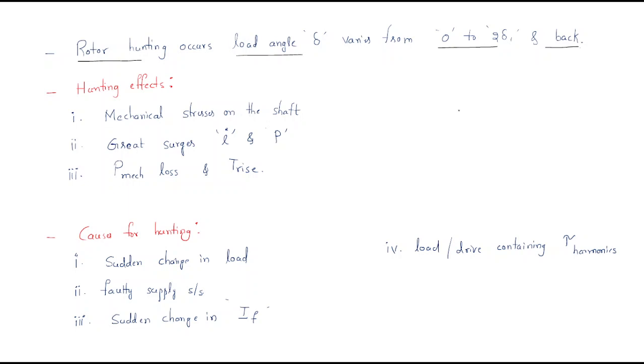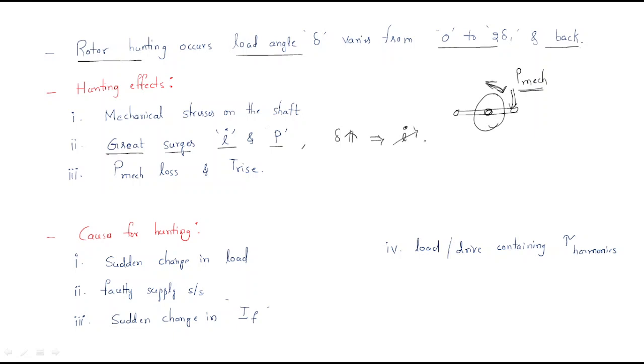The effects of hunting are as follows. First, mechanical stresses on the shaft: due to the load angle variation — increment and decrement — mechanical stress is applied on the shaft. Second, current and power surges: when the load angle varies, the current value also changes, and whenever the current changes the power also changes, causing surges.